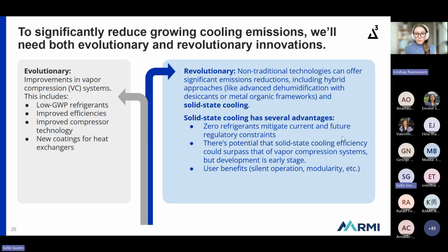As we look forward, we need to look at what we call revolutionary technologies, or the alternative cooling technologies, which I like that phrase as well. These are non-traditional approaches to cooling that can deliver significant efficiency gains. This includes hybrid approaches like liquid desiccants and metal organic frameworks, and on the active cooling side, things like solid state cooling. Solid state cooling uses solid materials to facilitate heat exchange, eliminating the need for refrigerants, which is a key advantage of this technology class, as it reduces climate impact and mitigates current and future regulatory constraints on refrigerants.